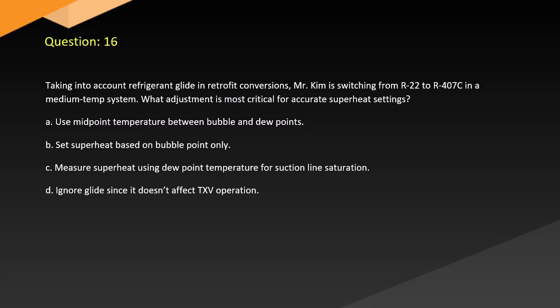A. Use midpoint temperature between bubble and dew points. B. Set superheat based on bubble point only. C. Measure superheat using dew point temperature for suction line saturation. D. Ignore glide since it doesn't affect the TXV operation.